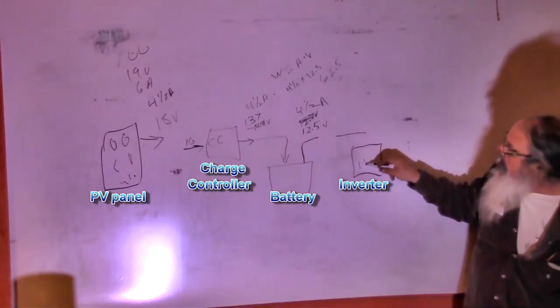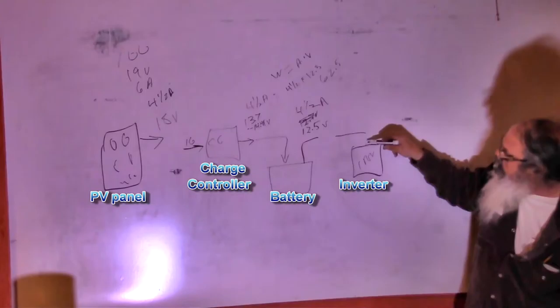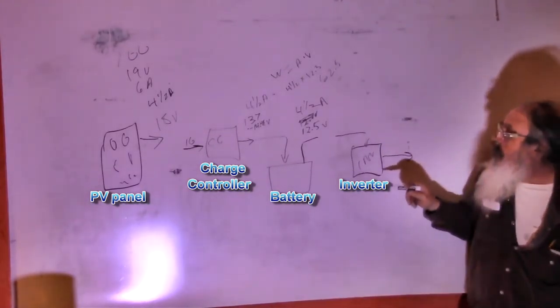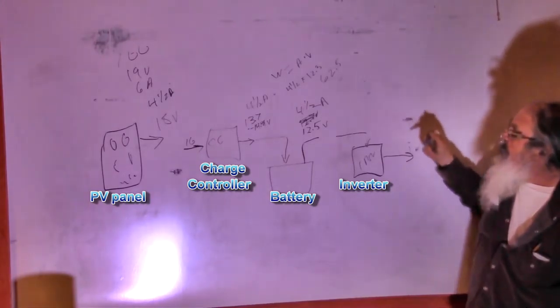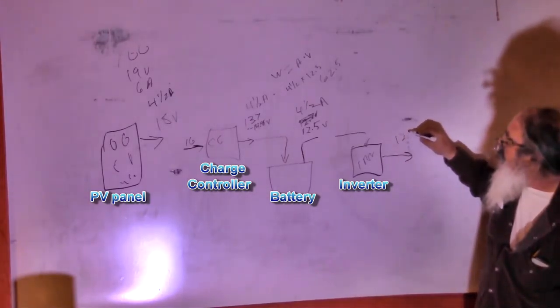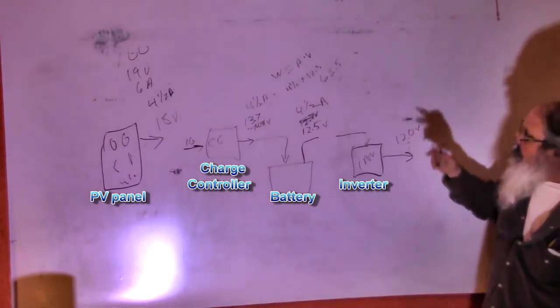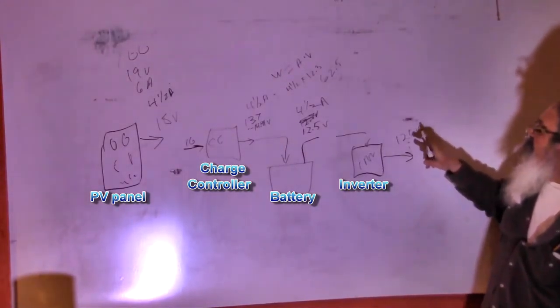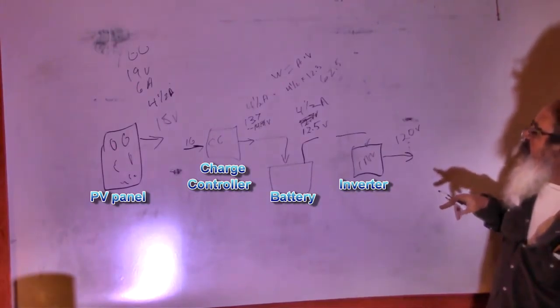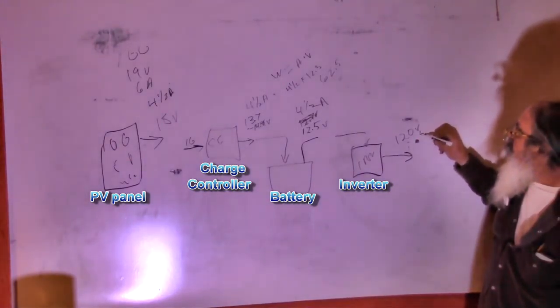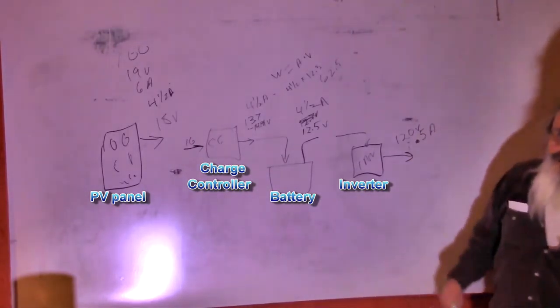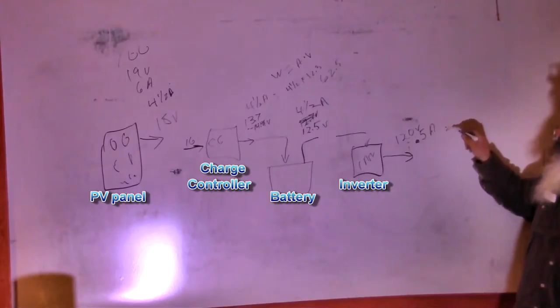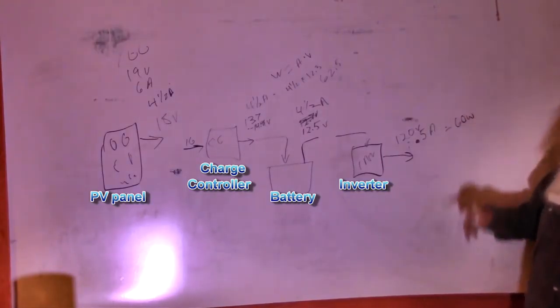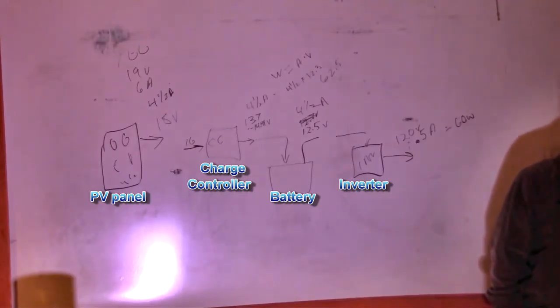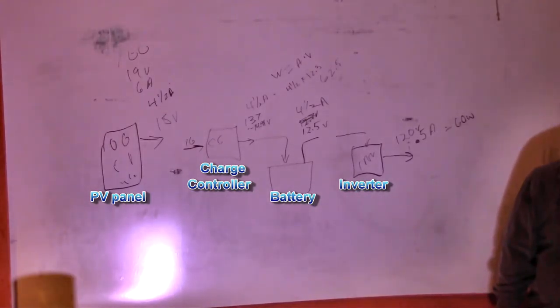This is your inverter. Going into it you have 62.5 watts, and out of it you'll lose a little bit. You're producing 120 volts, and watts is amps times volts, so 120 times what gets you to 62? Roughly 0.5 amps at 120 volts, which is more or less equal to 60 watts out of your inverter. That's the 60 watts you're going to use to try and run your 100 watt refrigerator, and it ain't gonna work.